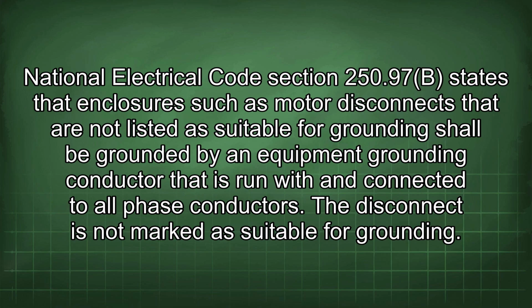National Electrical Code Section 250.97(b) states that enclosures such as motor disconnects that are not listed as suitable for grounding shall be grounded by an equipment grounding conductor that is run with and connected to all phase conductors. The disconnect is not marked as suitable for grounding.